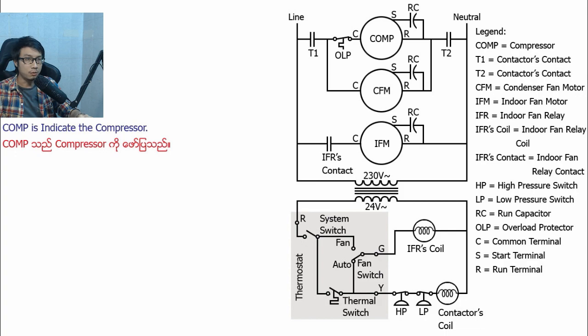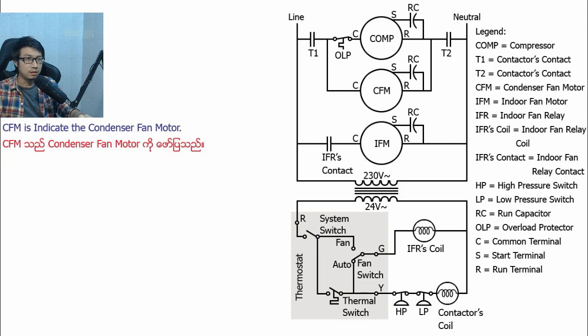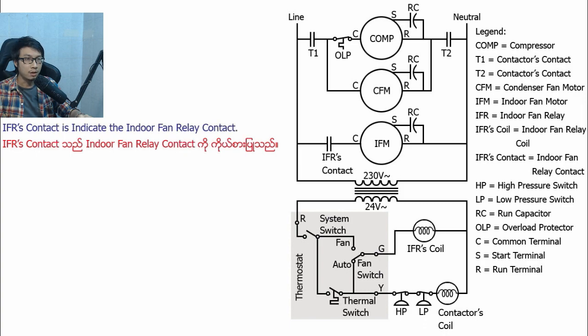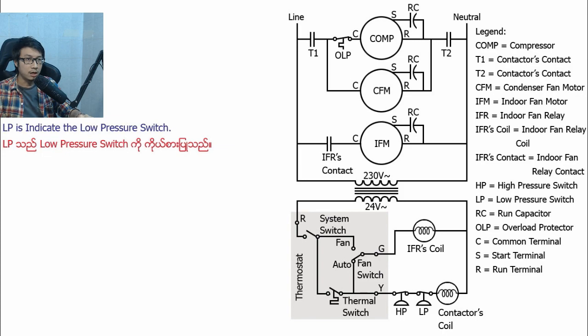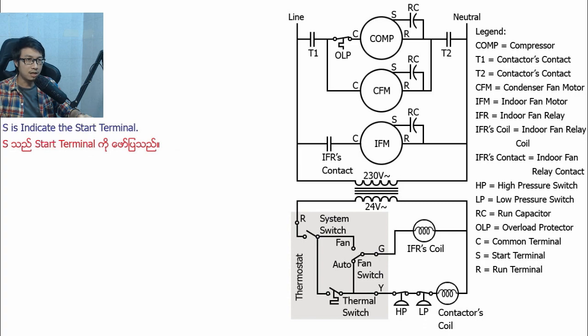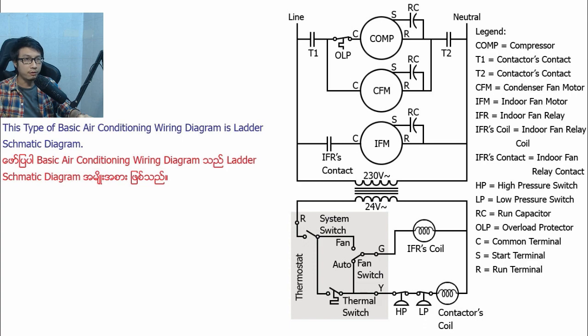COMP is the compressor. T1 is contactor's contact. T2 is contactor's contact. CFM is condenser fan motor. IFM is indoor fan motor. IFR is indoor fan relay. IFR coil is indoor fan relay coil. IFR contact is indoor fan relay contact. HP is high-pressure switch. LP is low-pressure switch. RC is run capacitor. OLP is overload protector. C is common terminal. S is start terminal. R is run terminal. This type of basic air conditioning wiring diagram is a ladder schematic diagram.